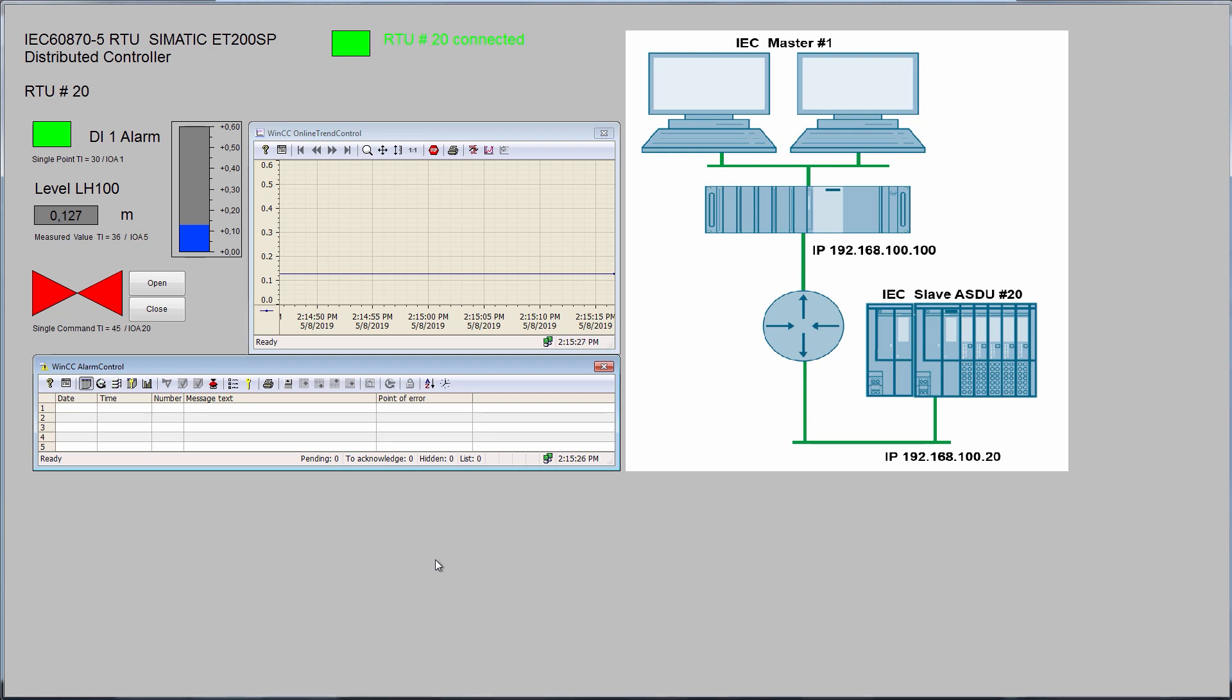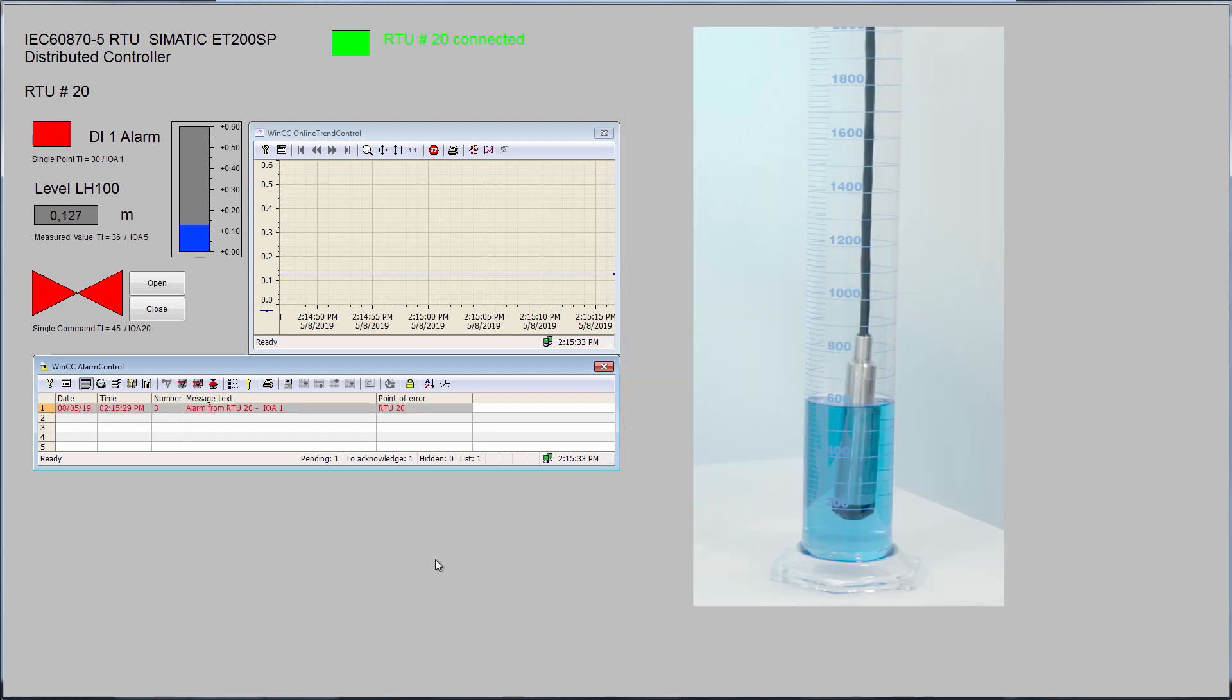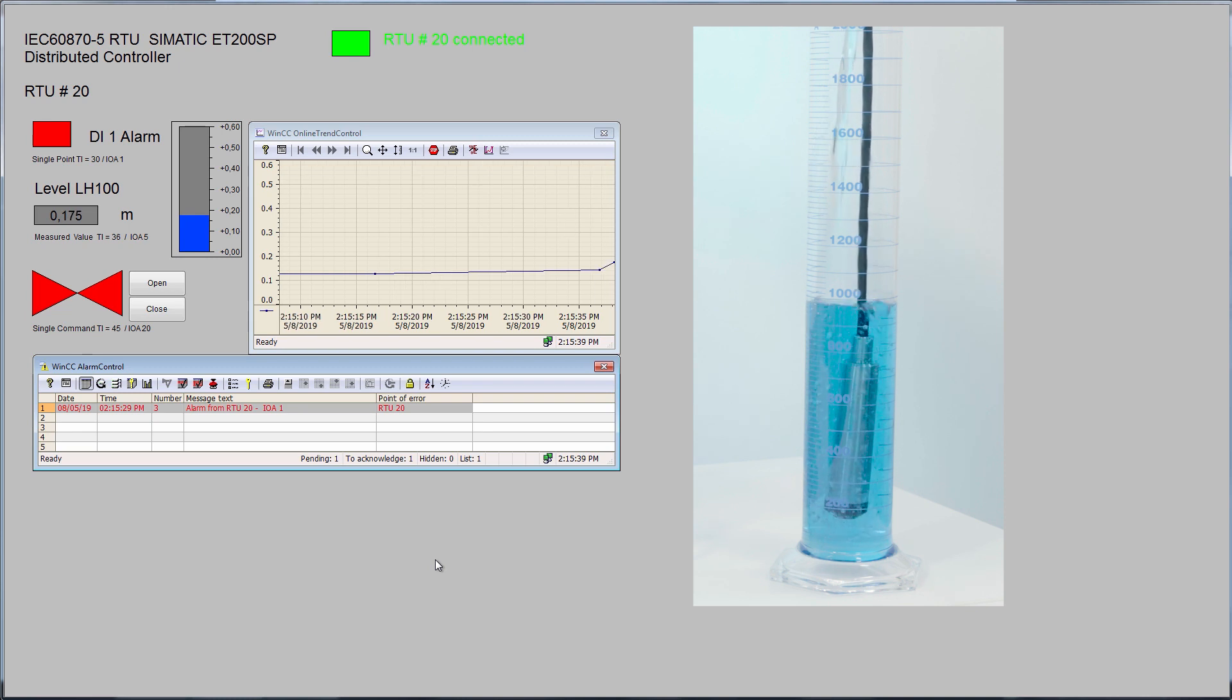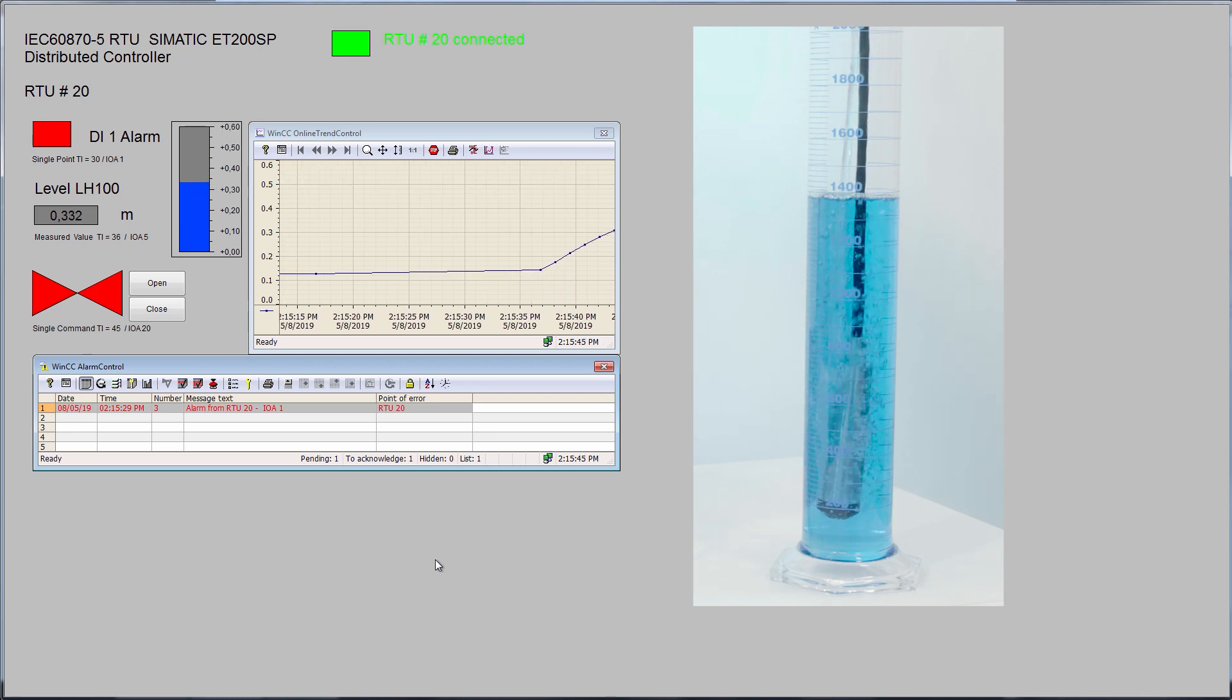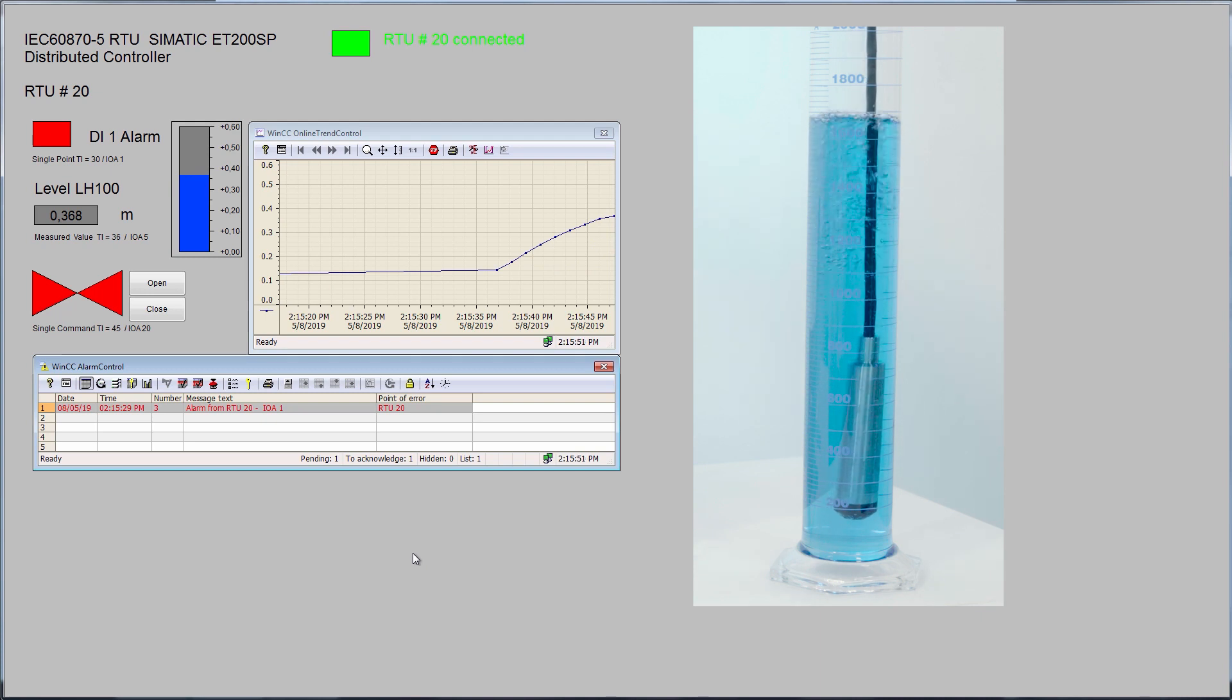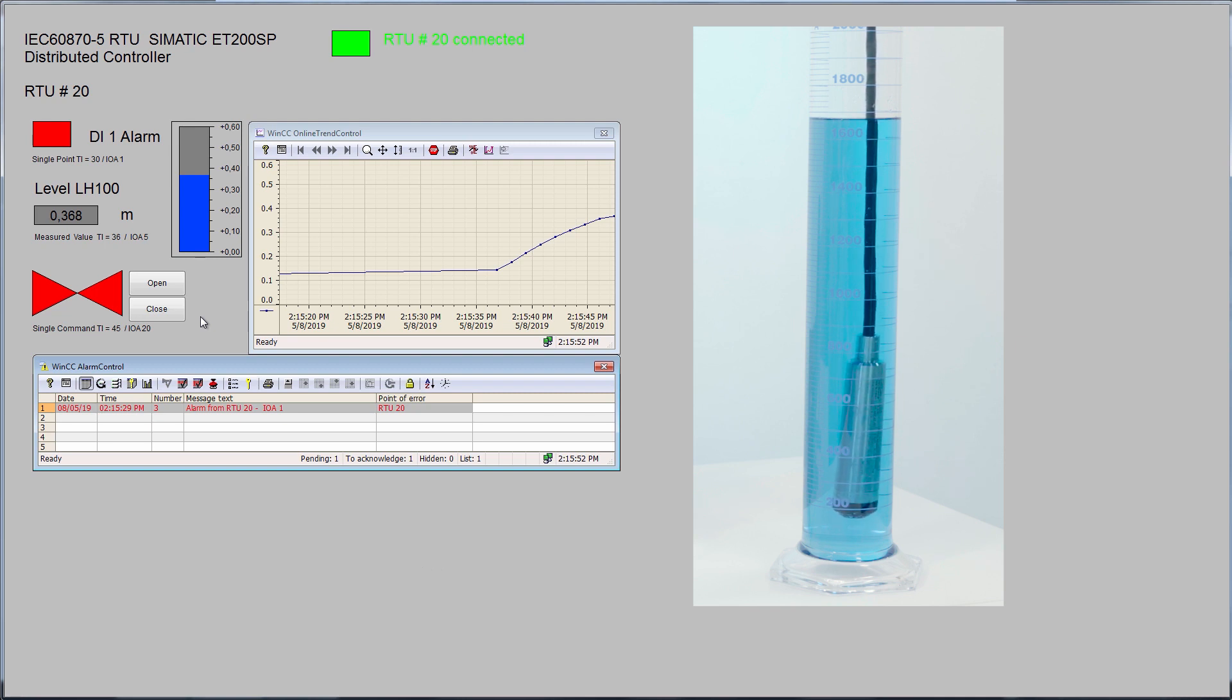If we trigger an alarm in the RTU, it will be displayed on screen and entered in the alarm list. Now I change the fill level in my measuring cylinder. The new fill level is detected by the LH100 sensor and transmitted to the control center. There it appears on the screen and inserted in the measured value archive with a timestamp.